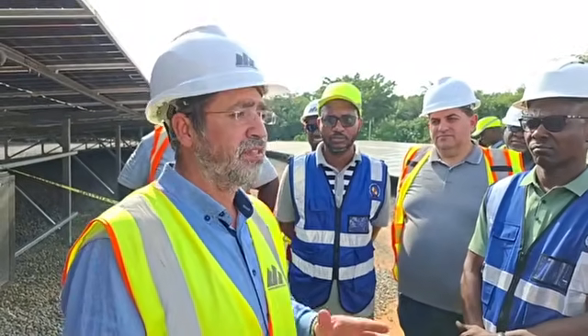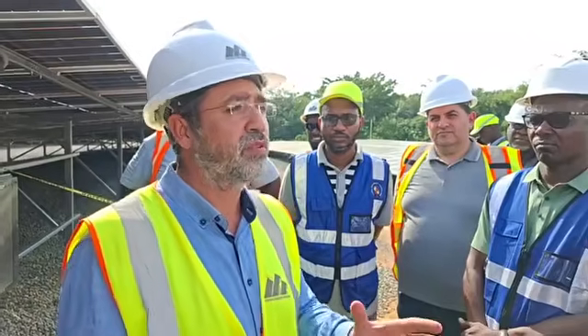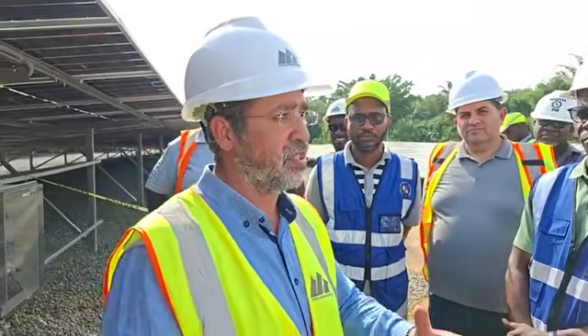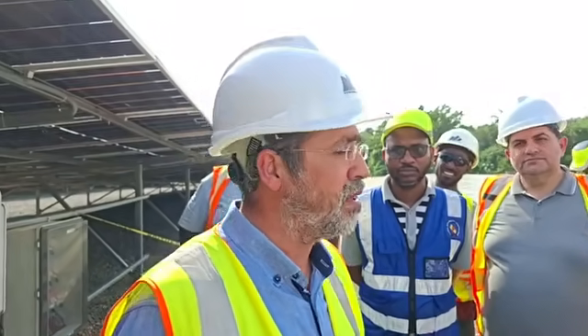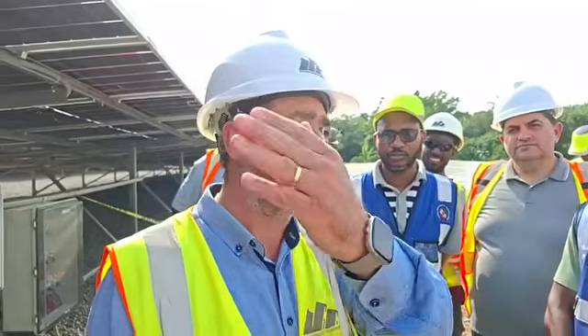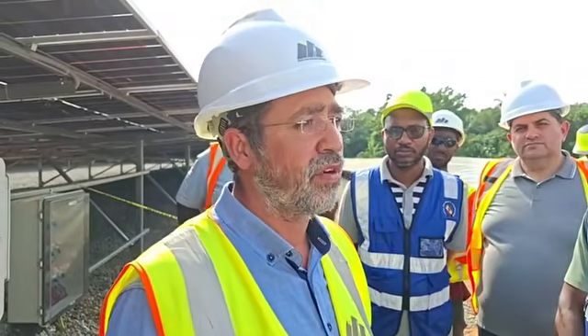And then we have 2 medium voltage stations stationed in every zone. The input is 800 volts AC and the output is 22 kilovolts, which goes directly to the medium voltage stations that we constructed already. And then there's one evacuation cable, medium voltage cable, that goes to the existing substation.